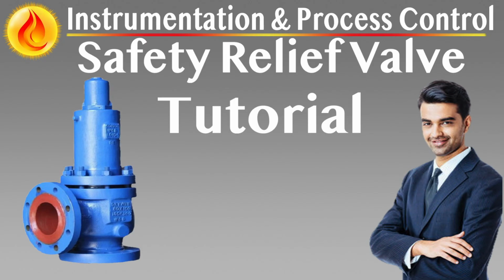Service compatibility and material pairing. The full wetted parts of the valve, seat, disc, nozzle, and trim must be compatible with process media properties, e.g. corrosivity, abrasiveness, operating and relief temperatures, pressure cycling, or pulsing, particularly in reciprocating compressor services. Material selection must consider both design, operating envelope, and emergency relief conditions, including fire exposure or thermal cycling.